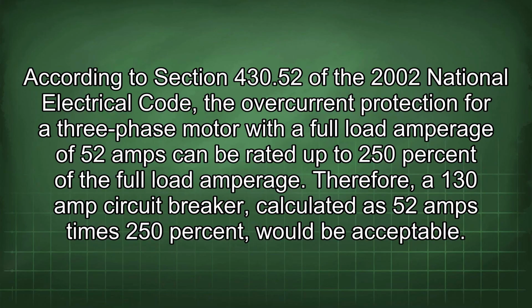According to Section 430.52 of the 2002 National Electrical Code, the overcurrent protection for a three-phase motor with a full load amperage of 52 amps can be rated up to 250% of the full load amperage. Therefore, a 130 amp circuit breaker, calculated as 52 amps times 250%, would be acceptable.